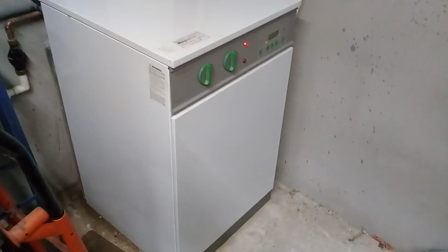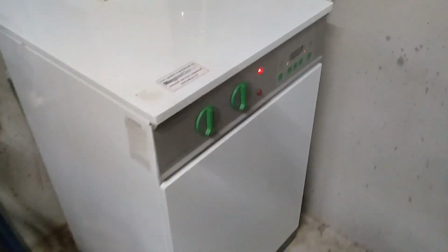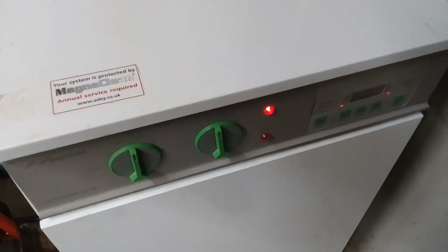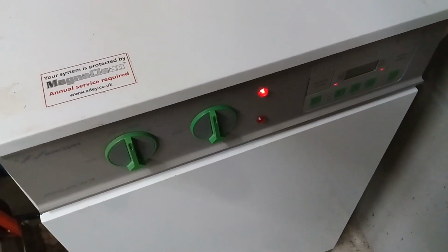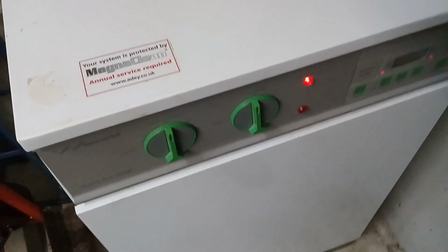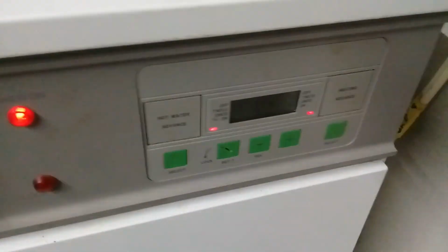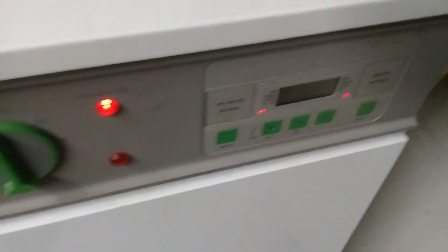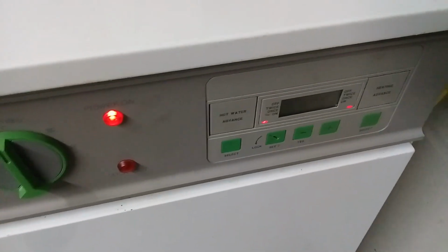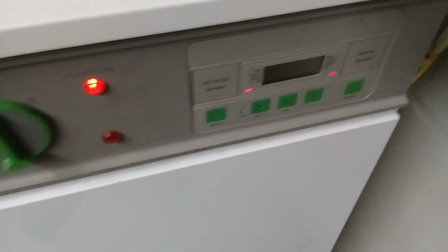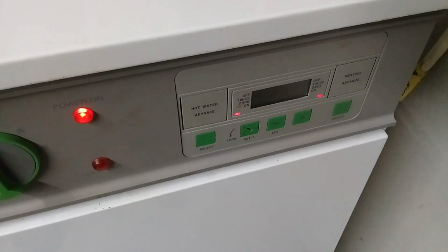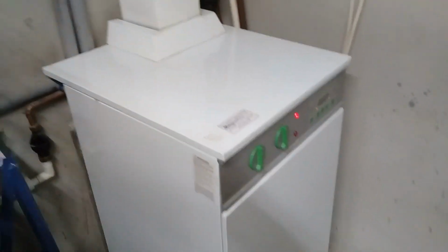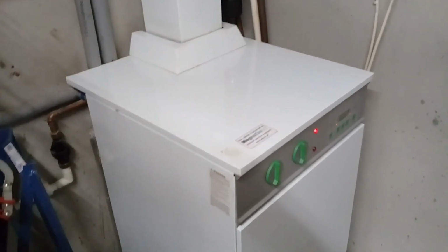The Worcester Bosch 1519 Heatslave oil boiler. Basically, the problem we had was that the central heating would get called. Hot water wouldn't. This is like hot water priority, so the heating's on, the hot water's called, it switches to hot water rather than heating. But with just the hot water on, we found that the radiators got really hot, and then the radiators would go lukewarm and back to hot again.